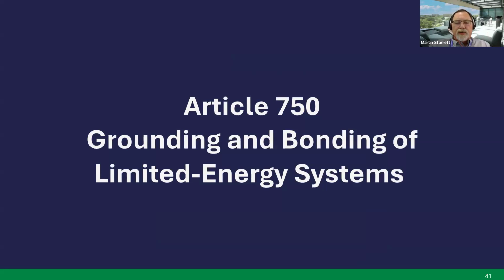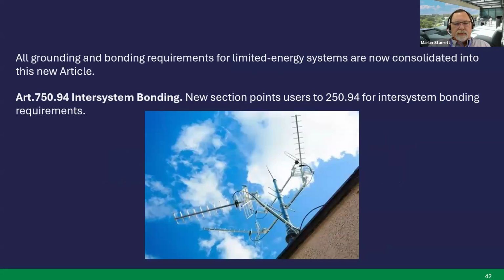Excuse me. Article 750 will contain all your grounding and bonding of limited energy systems. All the previous grounding and bonding, which was found in a whole bunch of different articles, is now consolidated in this article. One good example of removing some redundant language: Article 750-94, intersystem bonding, now carries you to 250.94 for intersystem bonding requirements instead of listing out the requirements previously in that article.